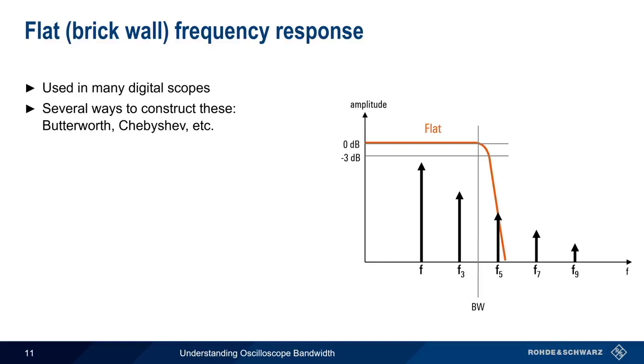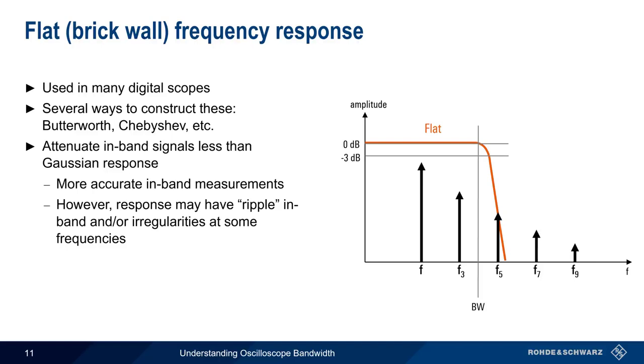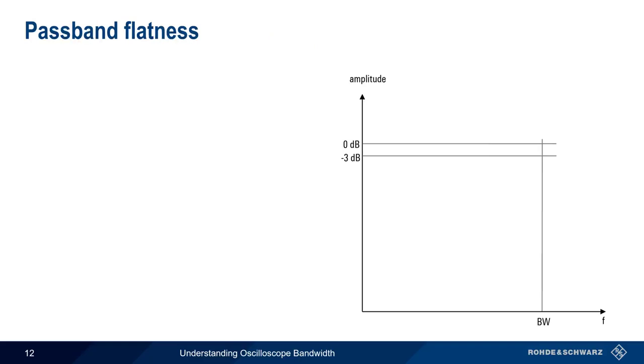Many digital oscilloscopes have a so-called flat or brick wall frequency response. There are several different ways to create this type of frequency response — for example, using filters with Butterworth or Chebyshev responses. Regardless of the implementation, scopes with a flat frequency response usually attenuate in-band signals less than those with a Gaussian response. In other words, there's very little attenuation until the 3 dB point is reached, after which amplitude falls off rather quickly. One advantage of this type of response is that it provides more accurate in-band amplitude measurements. However, note that the filter type may create some ripple in the pass band and/or irregularities at some frequencies. Another advantage of a flat frequency response is that it reduces the amount of out-of-band noise compared to a Gaussian response.